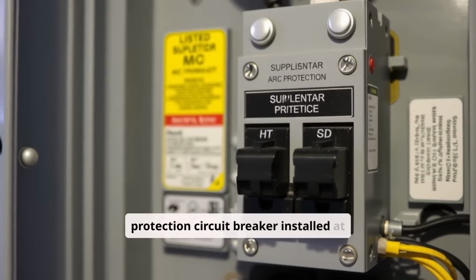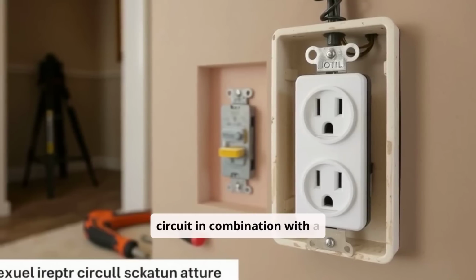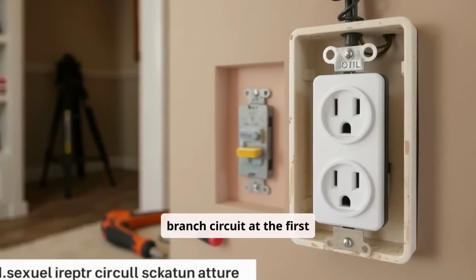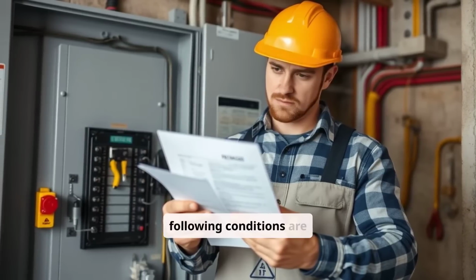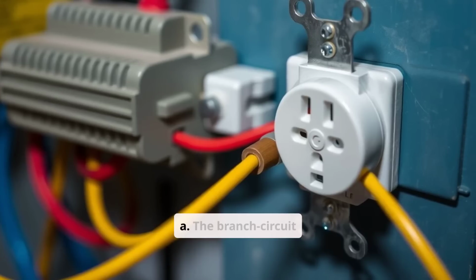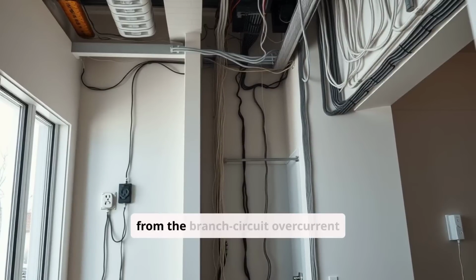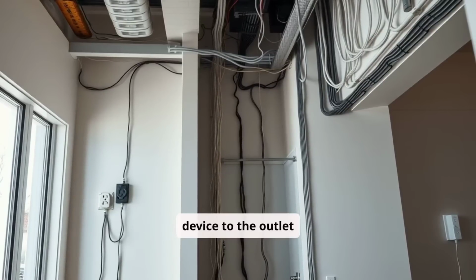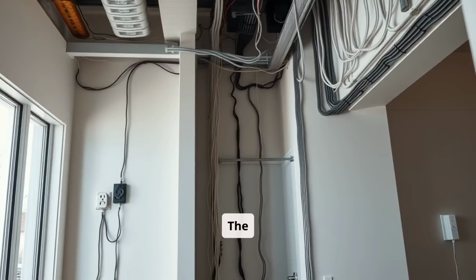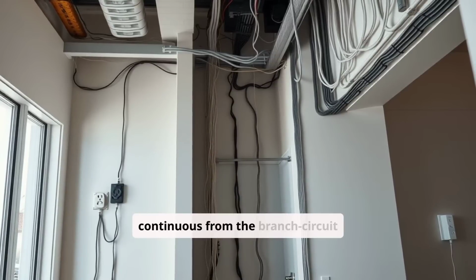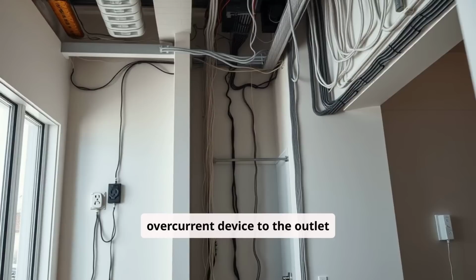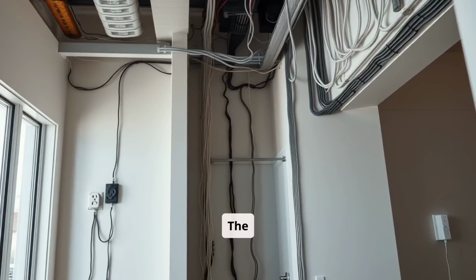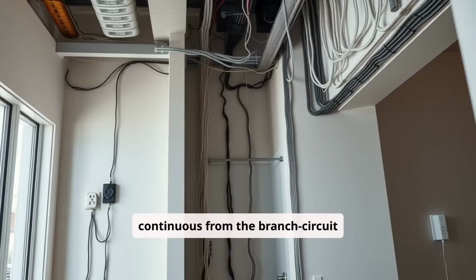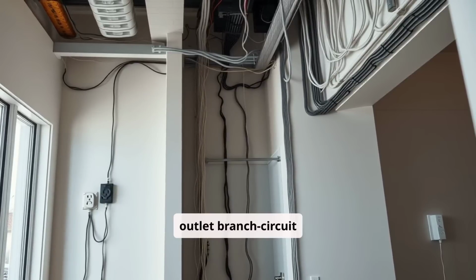3. A listed supplemental arc protection circuit breaker installed at the origin of the branch circuit in combination with a listed outlet branch circuit type AFCI installed on the branch circuit at the first outlet box if all of the following conditions are met. A. The branch circuit wiring shall be continuous from the branch circuit overcurrent device to the outlet branch circuit AFCI.